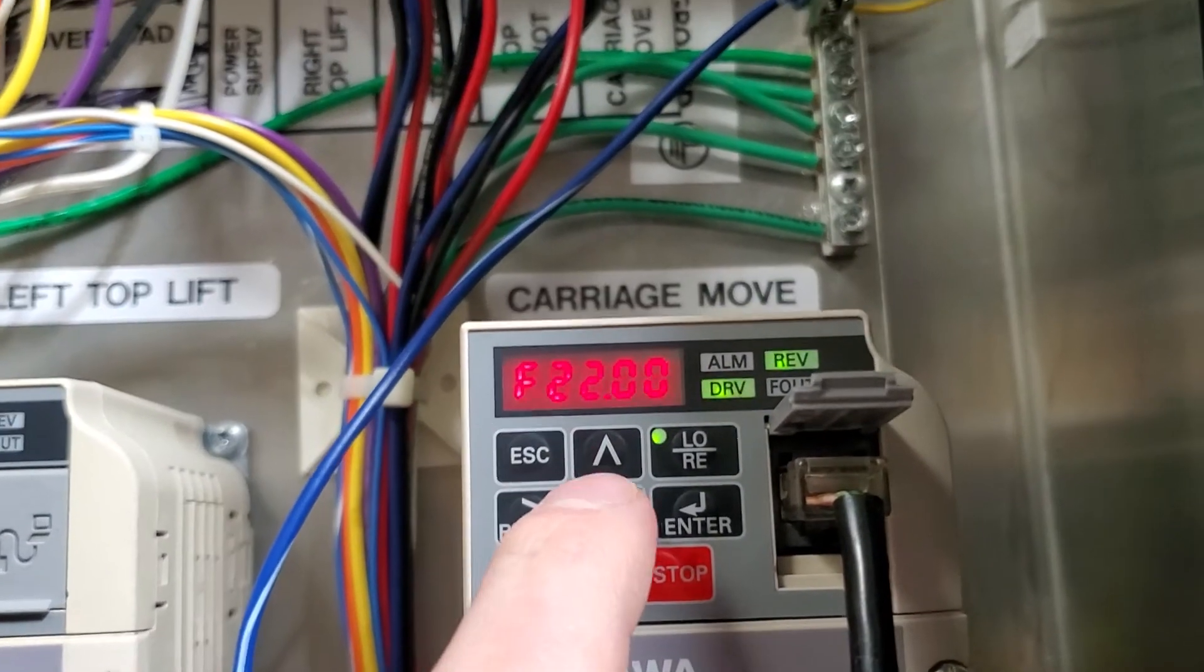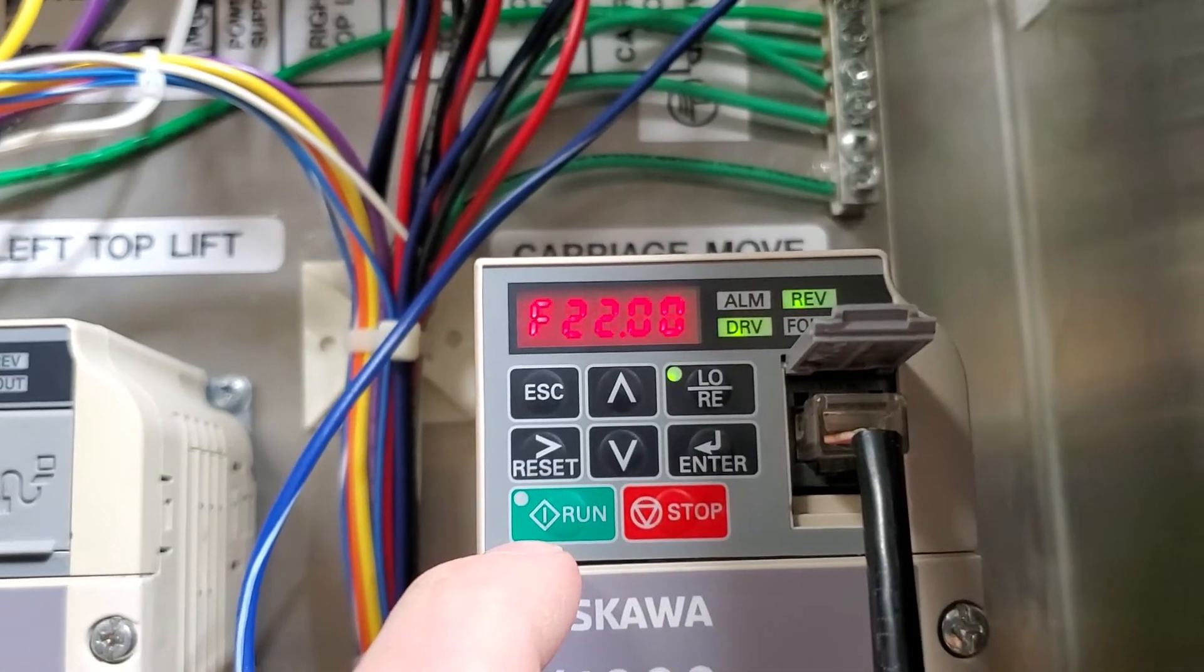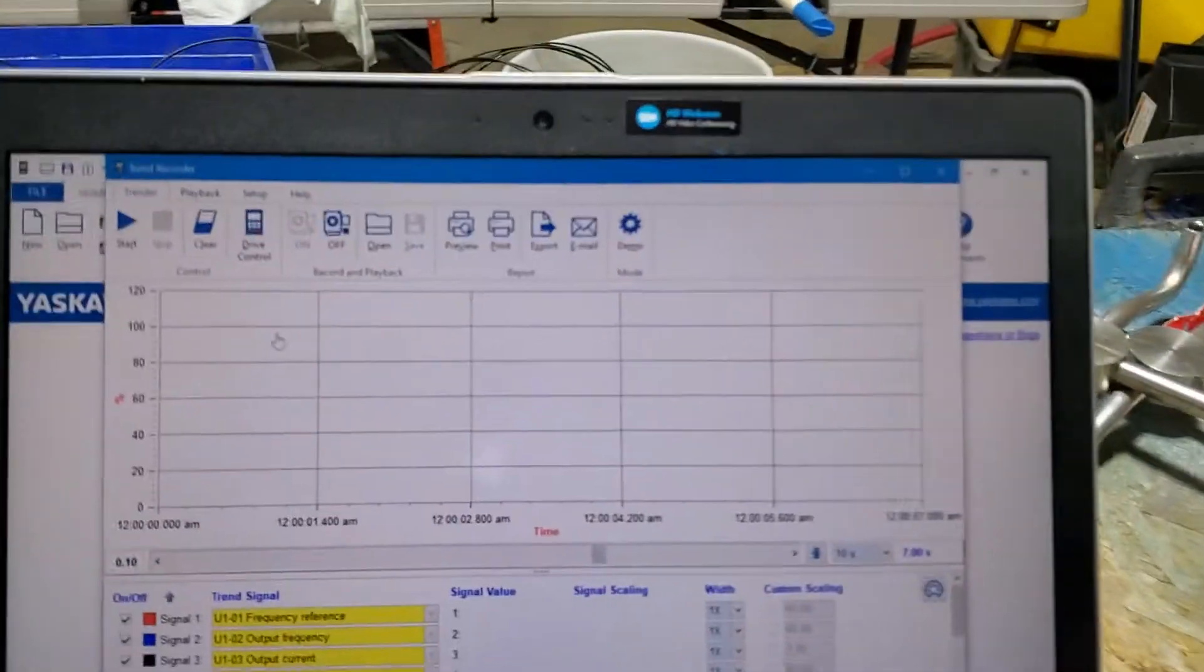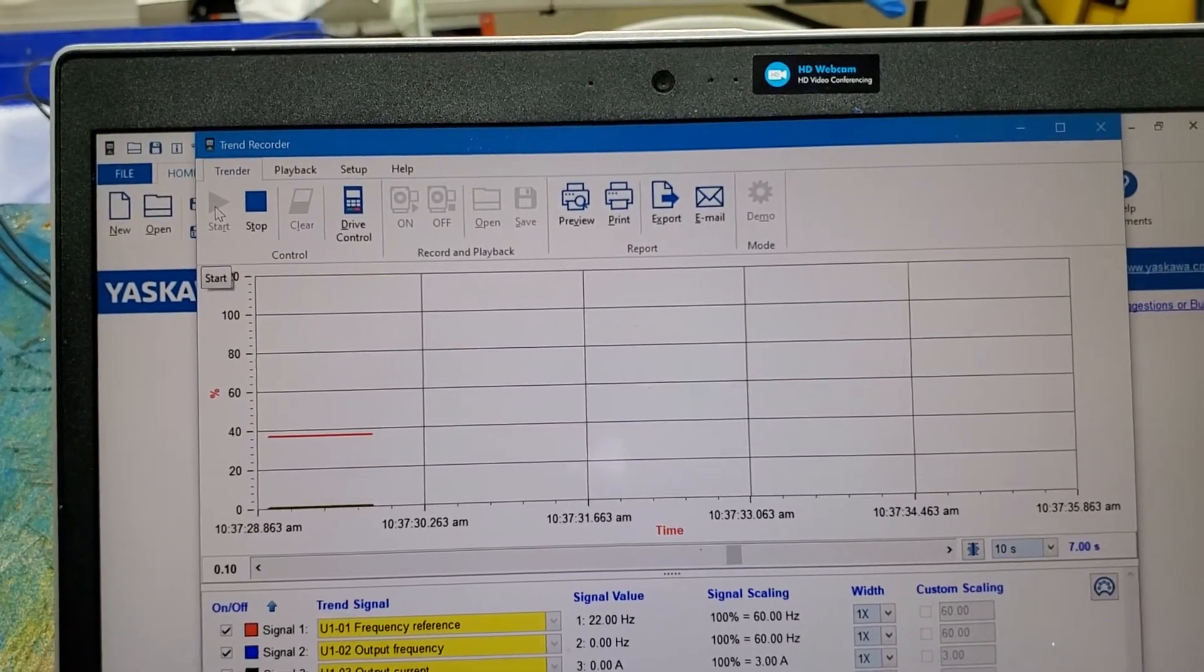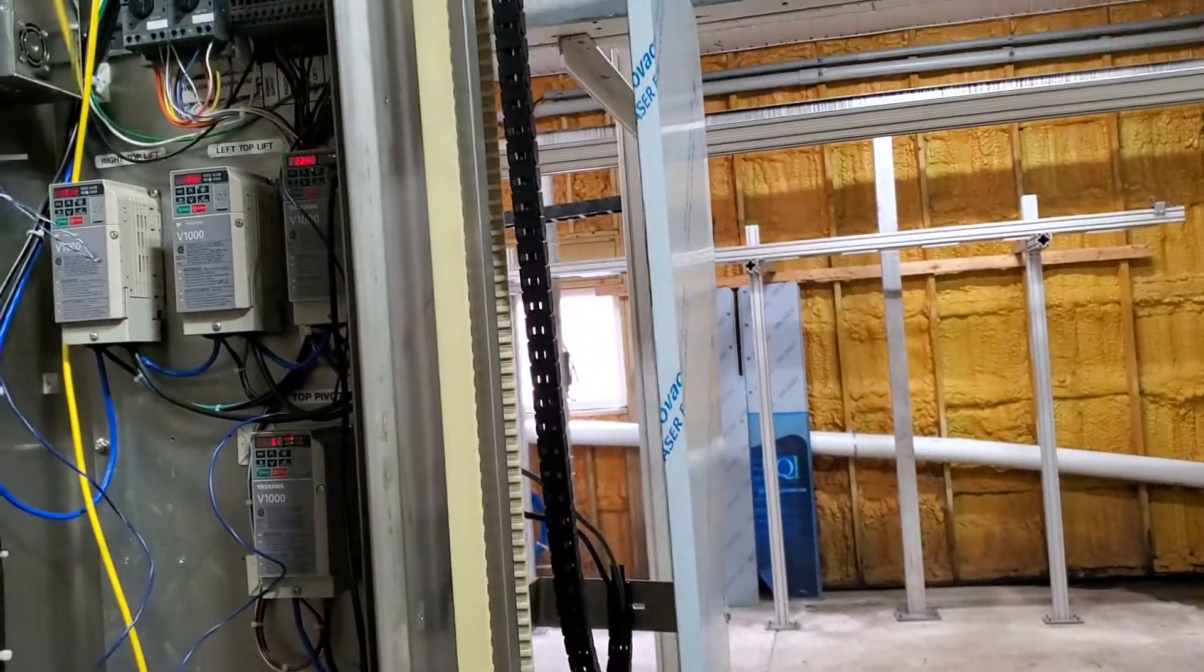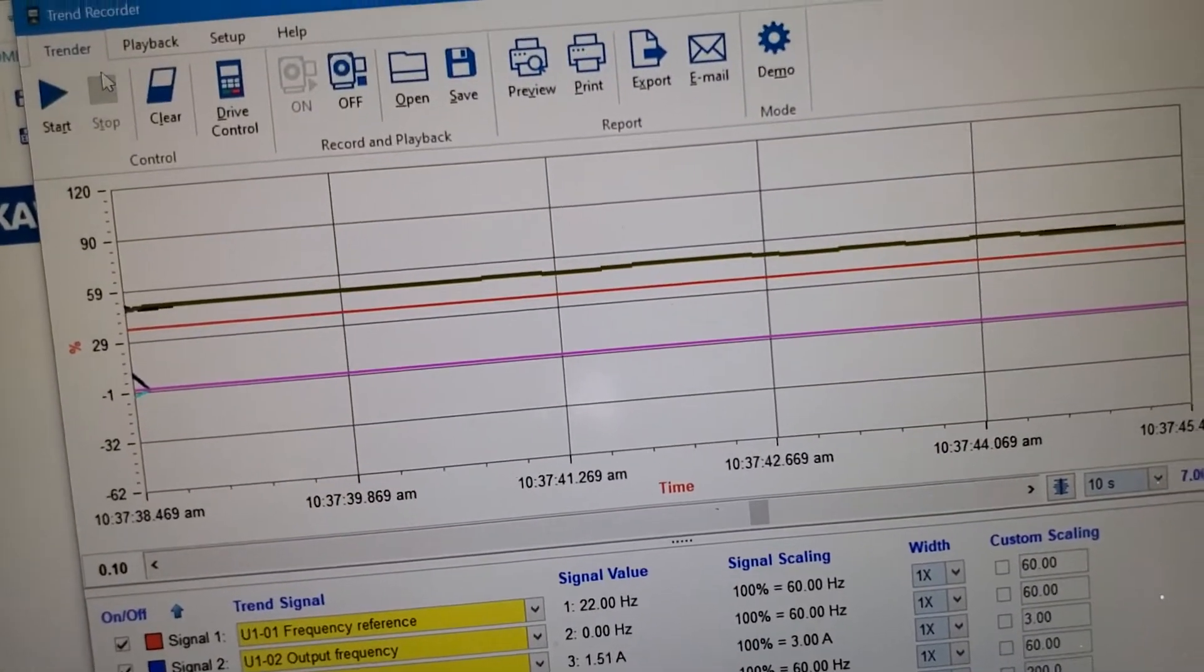So now we're going to be running forward at 22 hertz. What I'm going to do is hit start over here so I can start my capture. It starts recording data and then over here I'm going to hit run. The carriage runs away from me. I hit stop to stop it. You can see I collected the data, so I'm going to stop my data collection.